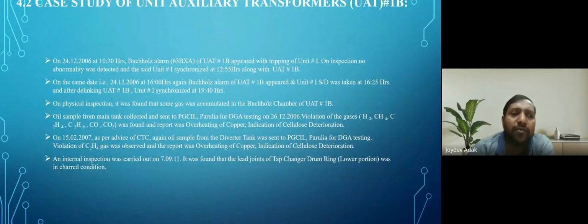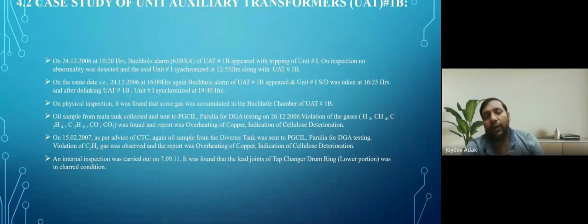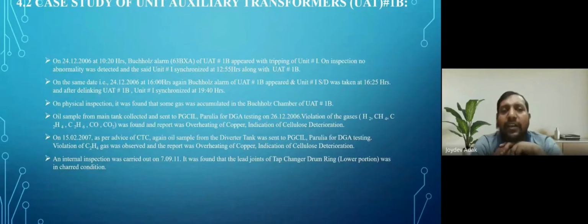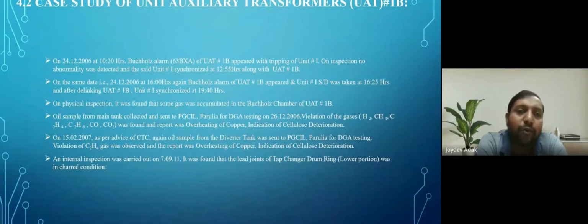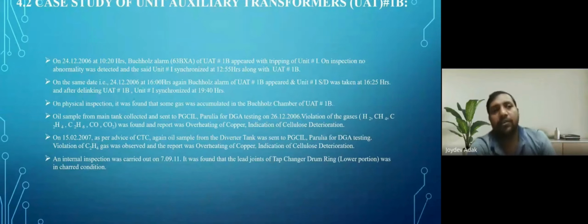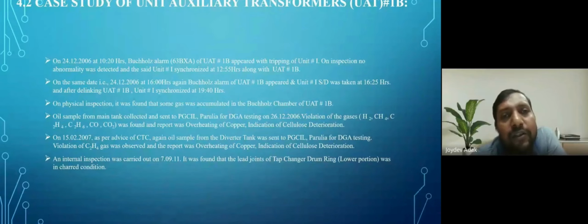Second one is UAT 1B. In 1B also there was a Buchholz operation. The most important protection of a transformer is Buchholz protection. Buchholz protection operates when any fault occurs inside the transformer and it creates gases, and it creates oxidation with the transformer oil and creates the dissolved gases of the transformer. These gases flow to the top portion of the transformer through the pipeline to the conservator tank, and the Buchholz relay is placed between the conservator tank and the transformer tank. So this gas is trapped in the Buchholz relay, and the Buchholz relay operates and immediately trips the unit as well as the UAT transformer. UAT means unit auxiliary transformer of a thermal power plant.